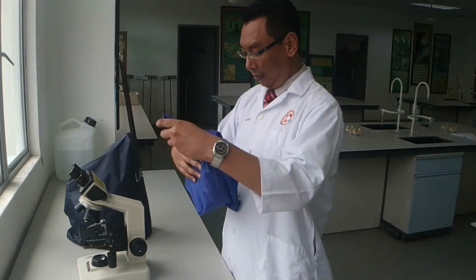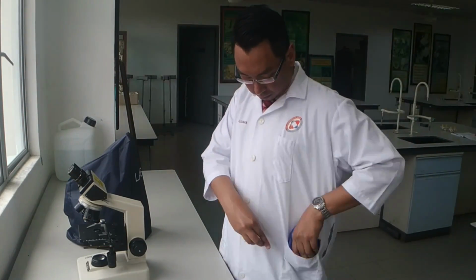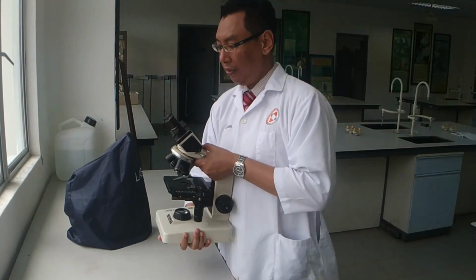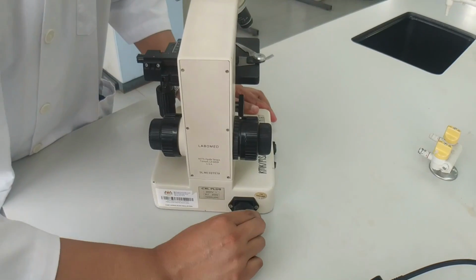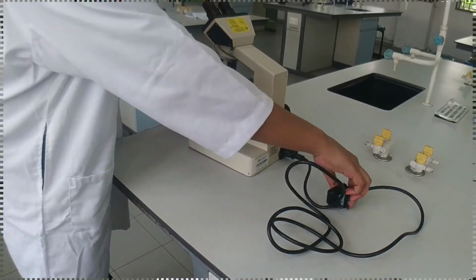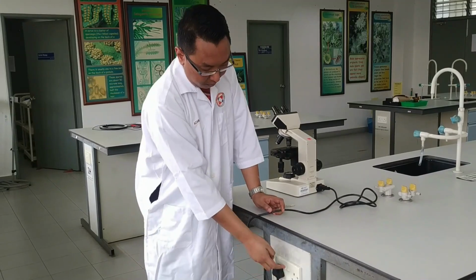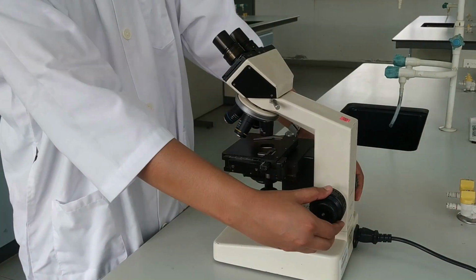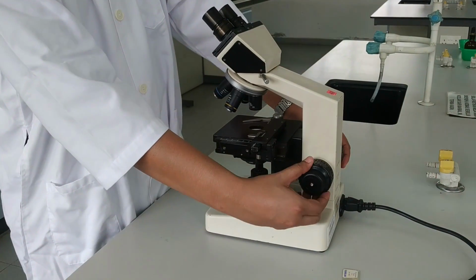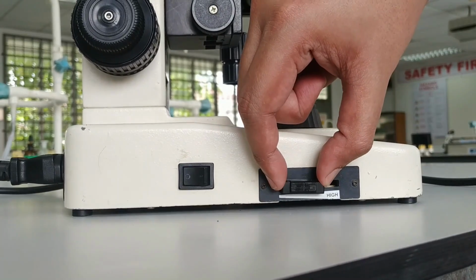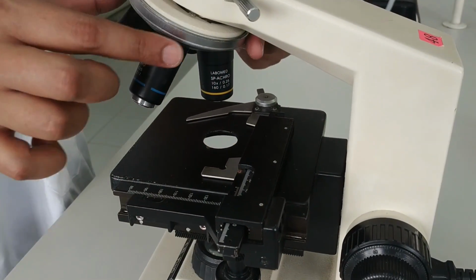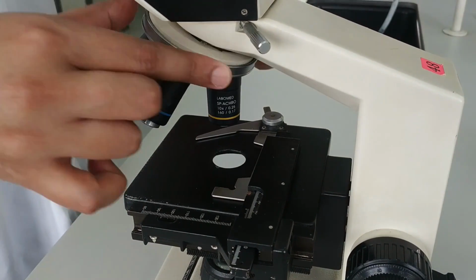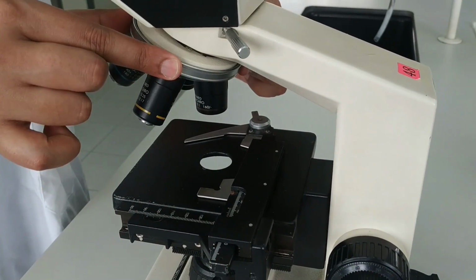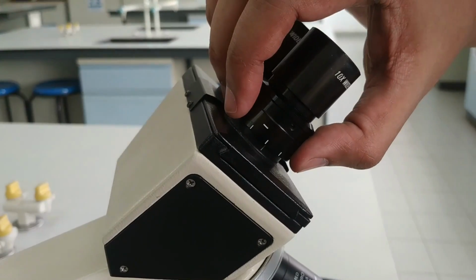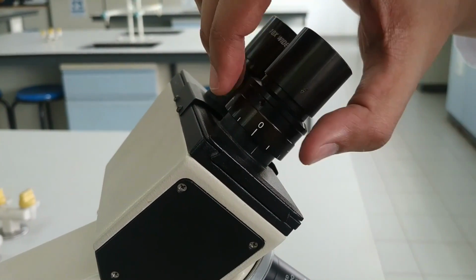Carry the microscope from the storage area to the working station with both hands. Connect the microscope to the power source by plugging in the wire. Check and make sure the stage is set at minimum level. Make sure the light control knob is set at minimum level. Make sure the objective lens is set to the scanning objective lens. Make sure the ocular lens is set to zero.